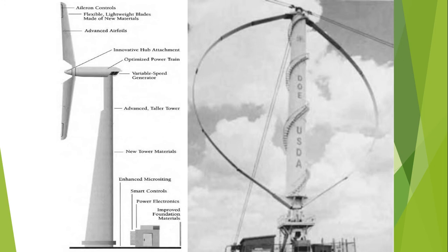A variable speed wind turbine allows the generator rotor speed to vary proportionally to the wind speed between the cut-in and rated speed, maintaining a constant and optimal aerodynamic performance above the rated speed. When the speed is higher than the rated speed, the generator rotor speed is held constant and the torque has to be actively controlled.